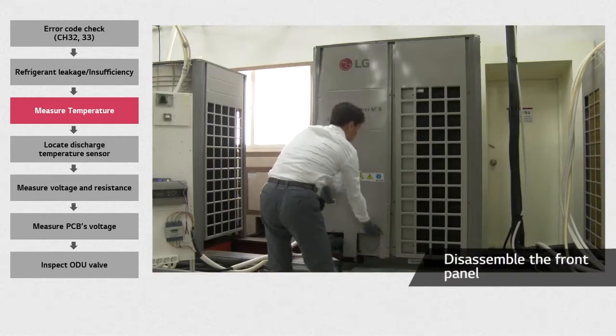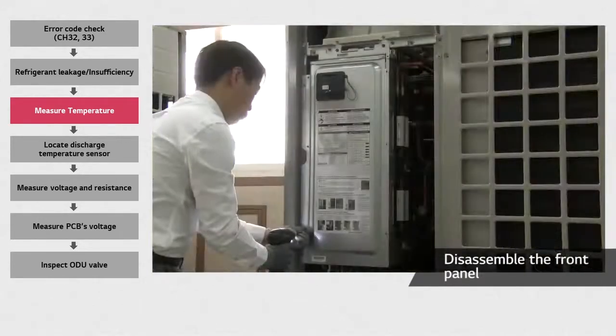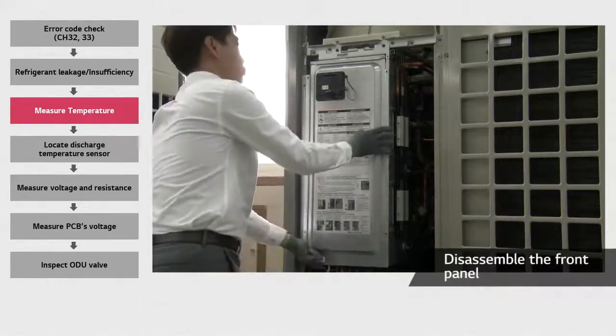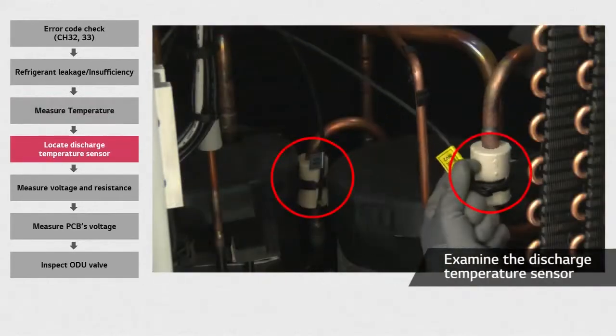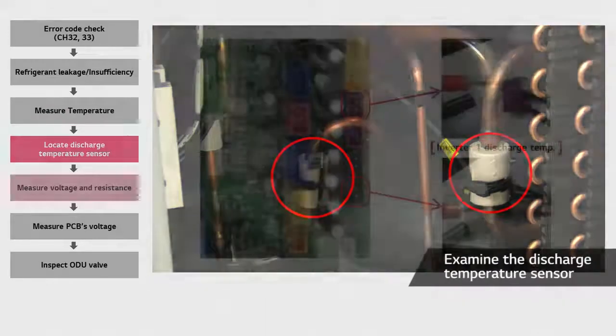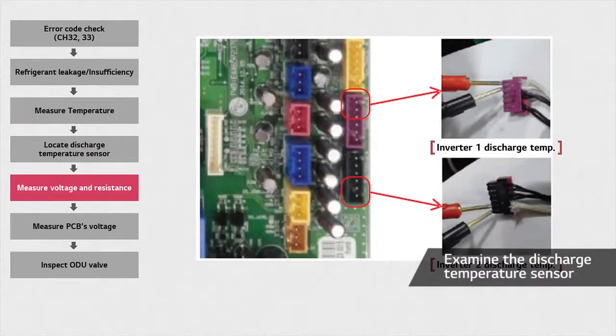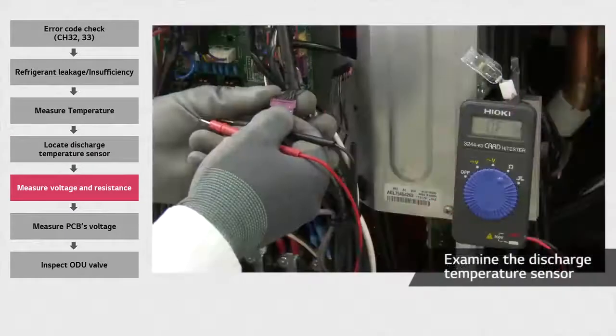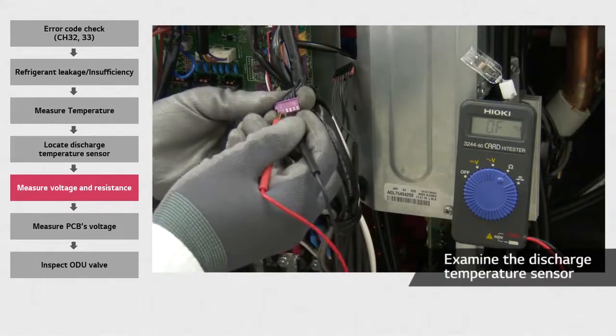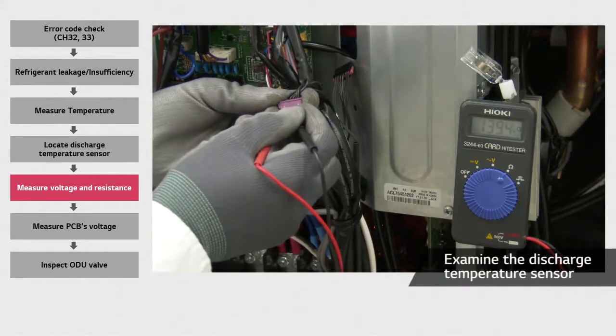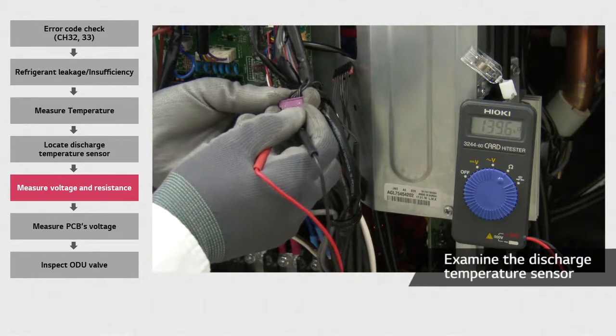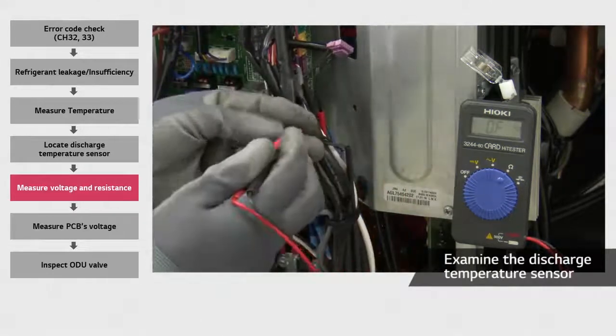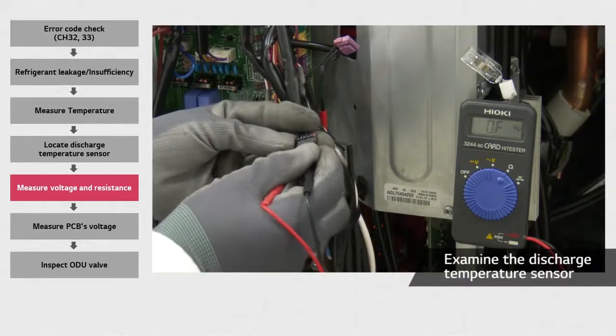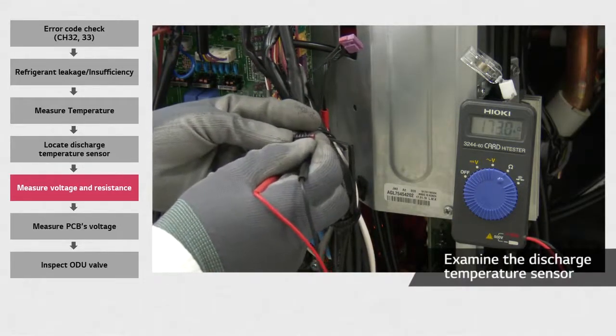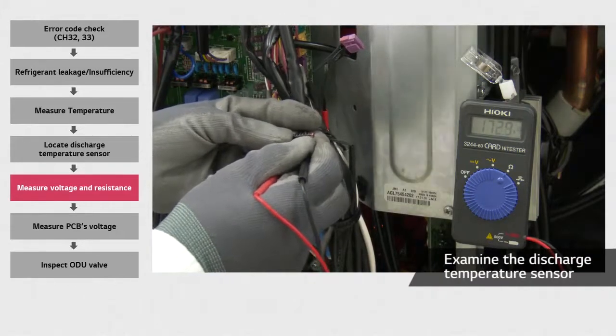First, remove the front panel on the outdoor unit, and then disassemble the control box of the outdoor unit. Check that the discharge temperature sensor is in the proper location. Measure the resistance across the two lines of purple and black connectors connected to the external PCB. This error will occur if the value is greater than 5 megaohm or smaller than 2 kiloohm. If the resistance value is in range and it matches the discharge temperature, the discharge temperature sensor is normal. See the guidebook appendix for more details about resistance values.